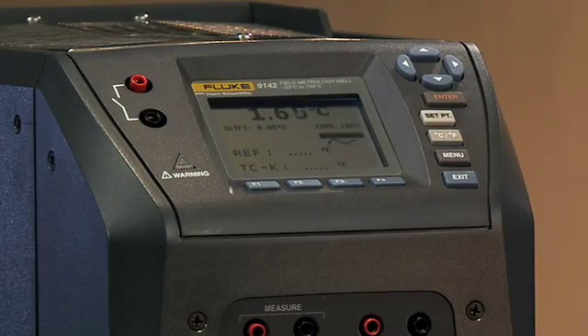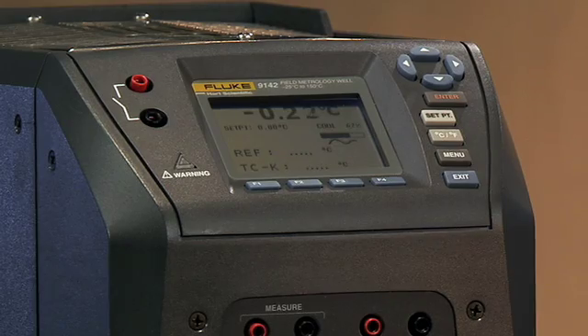Right down below that, you'll see we have 'ref' and 'TC-K' — that will only appear there if you have the process electronics. That's the ability to read a reference probe or a thermocouple, which I'm going to show you in a minute. So that's an introduction to the screen: you have your basic block temperature, your set point temperature with information about power percent heat and percent cool, the stability indicator, and then your reference temperature and the unit under test temperature for the process electronics option.